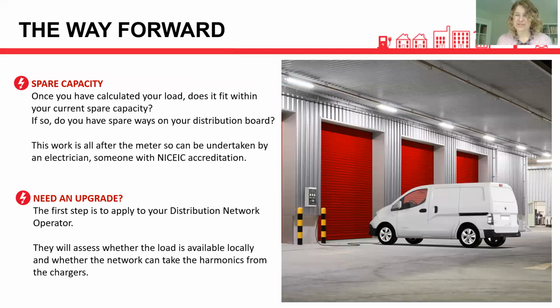So once you've thought about chargers and the load you require, where do you go next? First off, if you don't need much load, do you have existing spare ways on your distribution board? If so, great. If not, a new distribution board. This works all after the meter, so it can be undertaken by an electrician, for example somebody with NIC EIC accreditation.